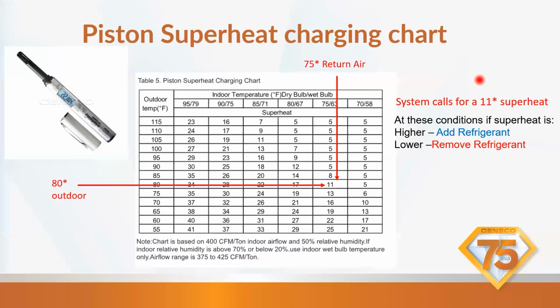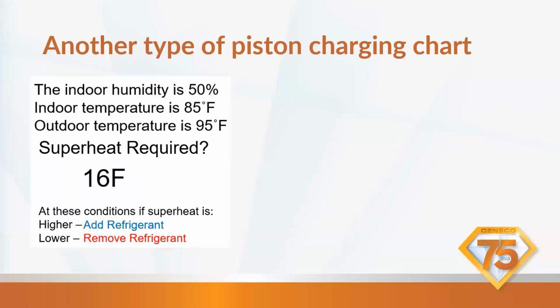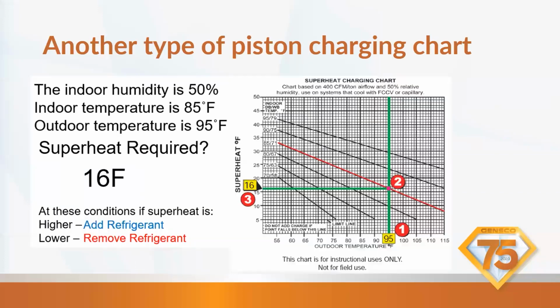I just wanted to touch on this real quick. Another type of piston charging chart is this one, right? So your indoor humidity is 50%. Your indoor temperature is 85, right here, 85. Your outdoor temperature is 95. We're going to come up and intersect. We want a 16-degree superheat. So you may need... the slides aren't moving for you.